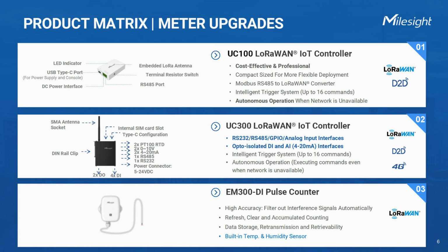The UC100, UC300 controllers, and EM300-DI, all of them are designed for meter upgrades. Then what's the difference? Number one, the interface type. The UC100 controller features the RS485 interface only, so it converts Modbus protocol to LoRaWAN or to Milesight D2D, vice versa. While UC300 features more industrial interfaces, besides the RS485, the industrial port RS232, digital input and output, analog input including 0 to 10 voltage, 4 to 20 milliamps, PT100 RTD temperature monitoring are all available in UC300.